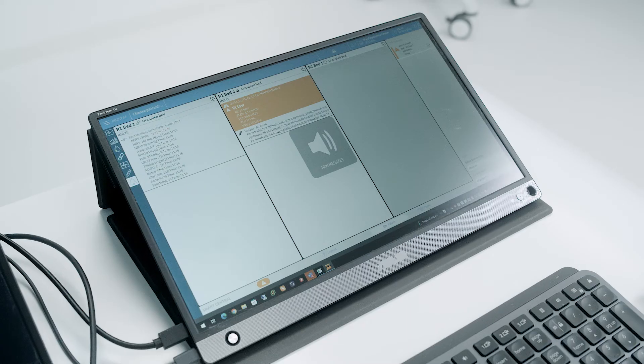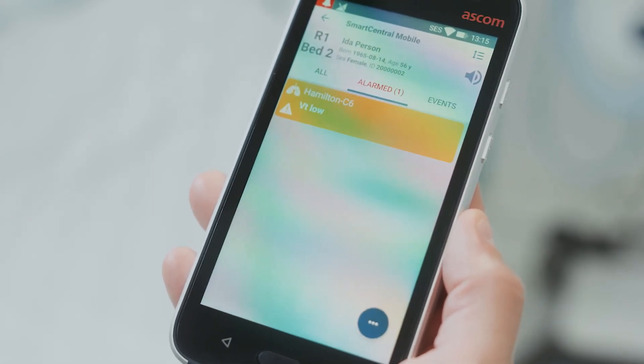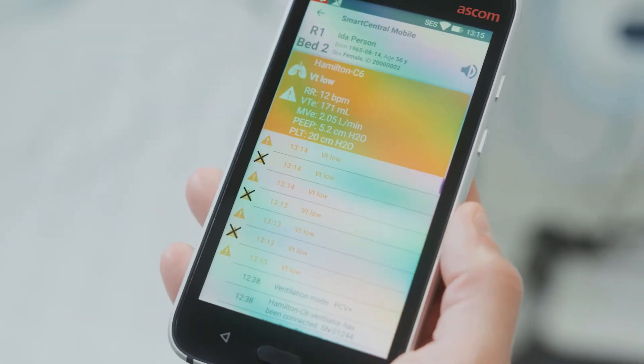Now for some technical info. What is the status of the alarms in terms of primary and secondary alarm status? The bedside devices delegate responsibility for primary alarm notifications to the ASCOM alarm management platform, which includes notifications going to dedicated dashboards as well as to mobile devices. Is this ASCOM solution limited to bedside devices that are able to be part of a distributed alarm system?